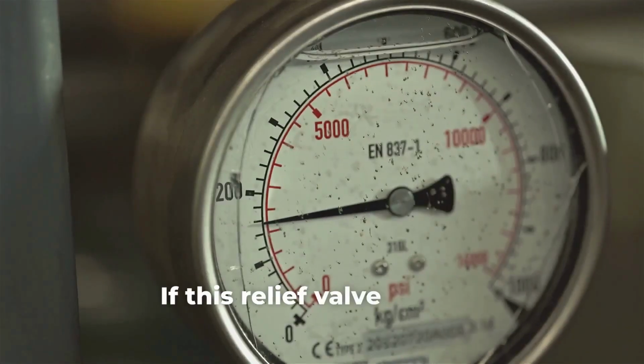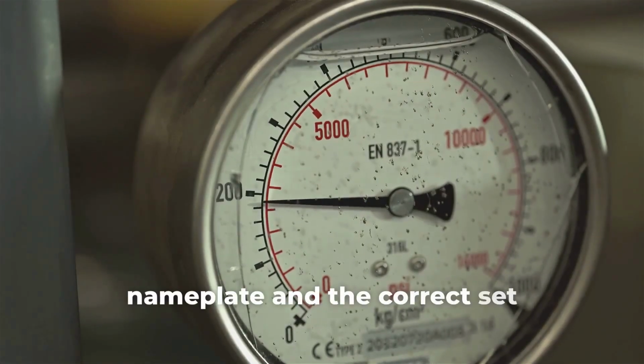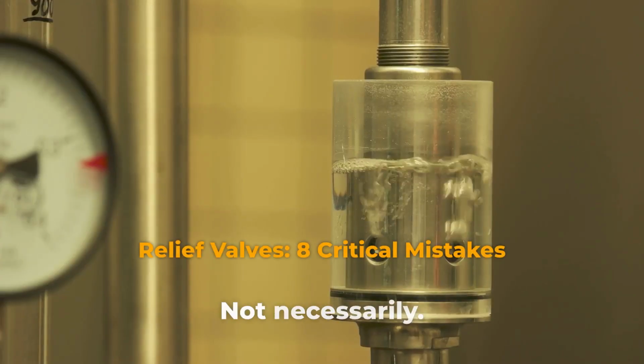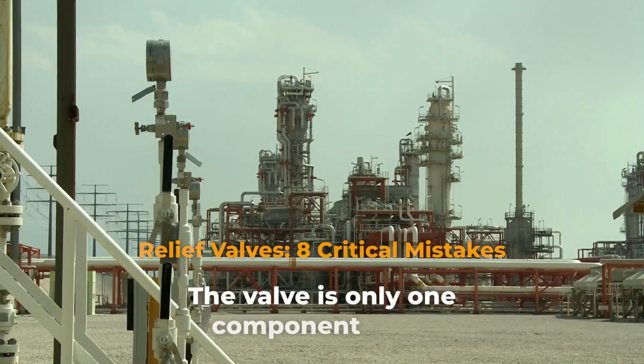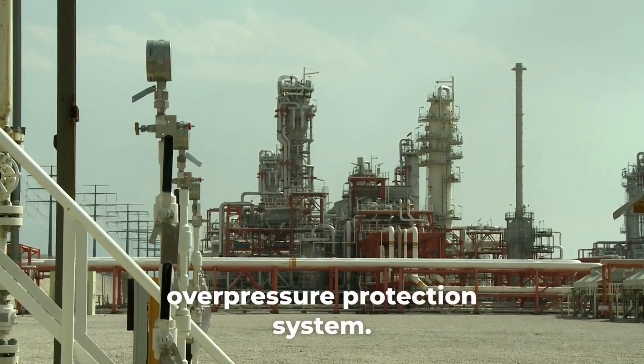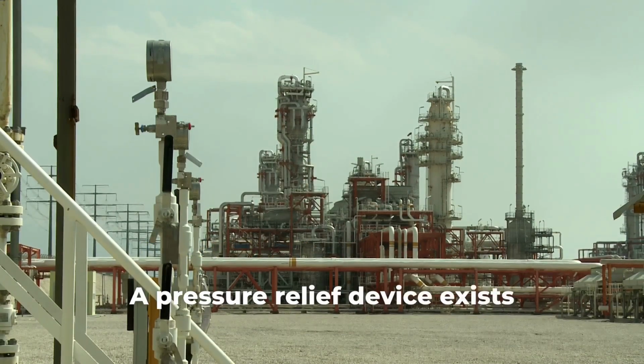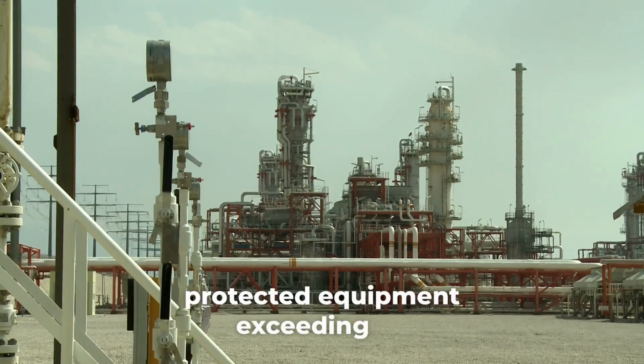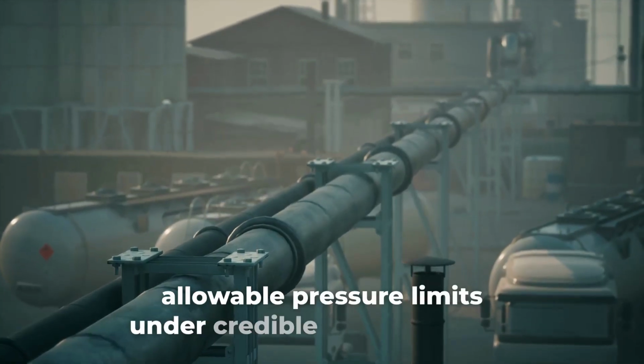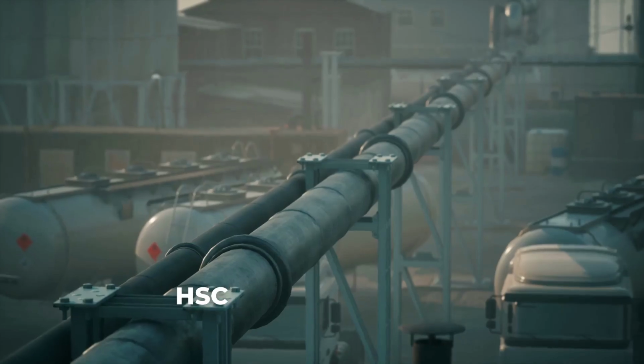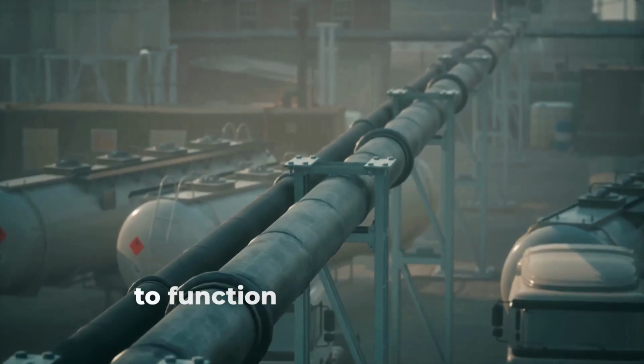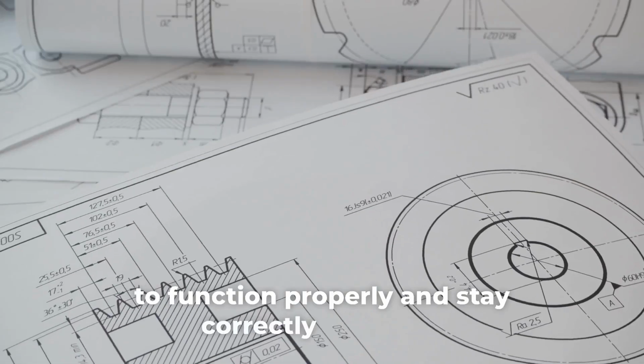If this relief valve has the correct nameplate and the correct set pressure, are we safe? Not necessarily. The valve is only one component of an overpressure protection system. A pressure relief device exists to stop protected equipment exceeding its allowable pressure limits under credible contingencies. HSE guidance requires protective devices to function properly and stay correctly adjusted.